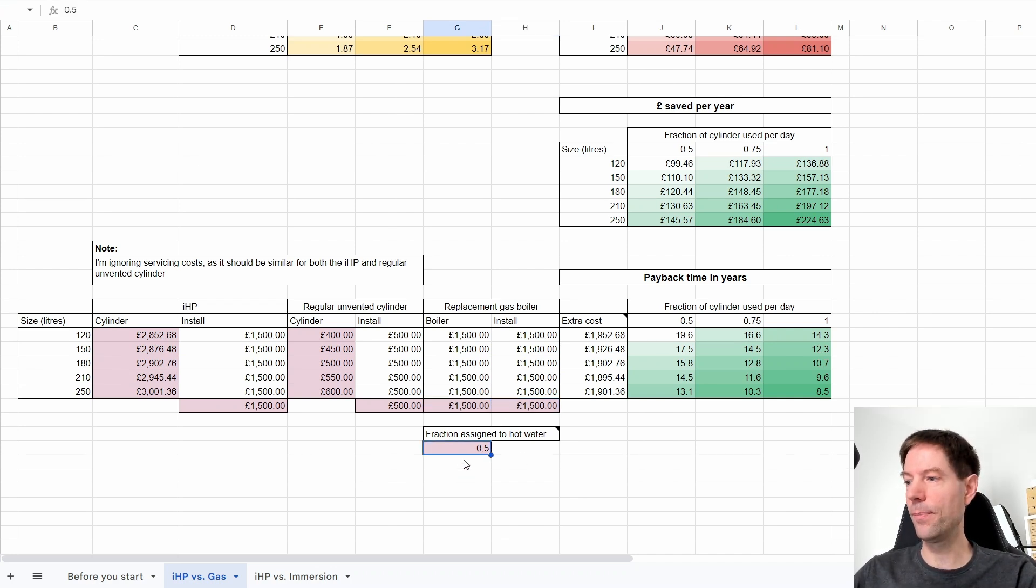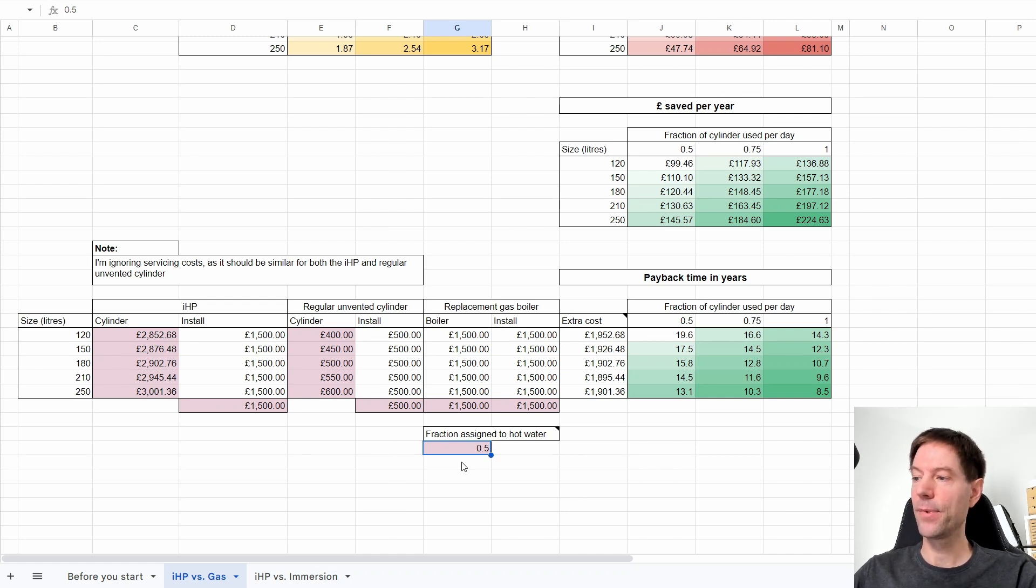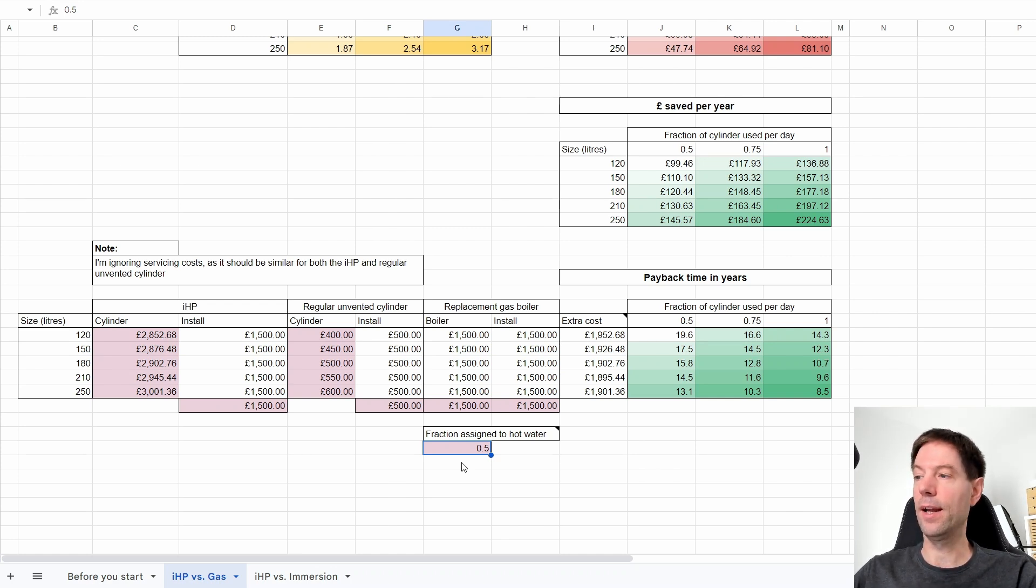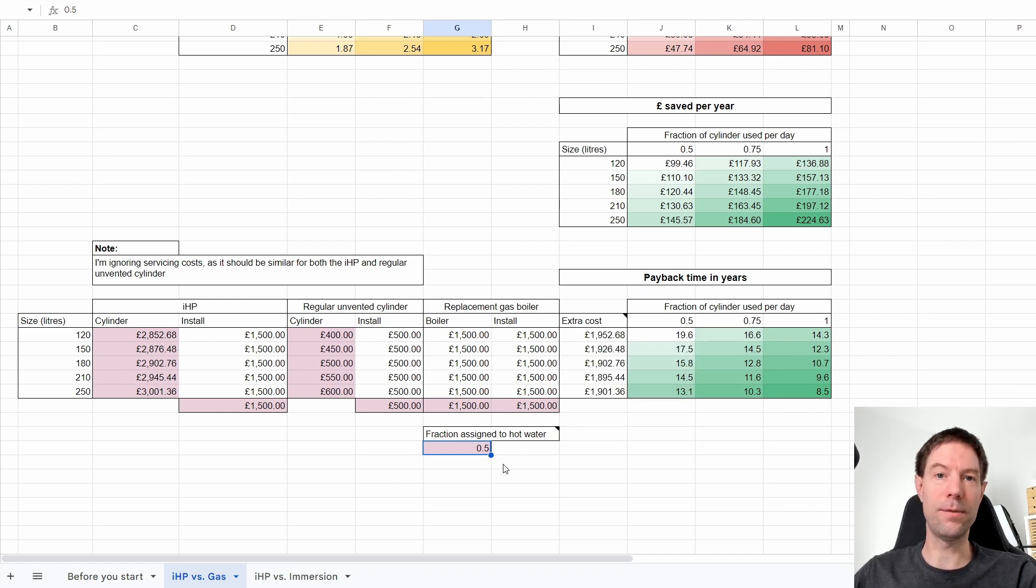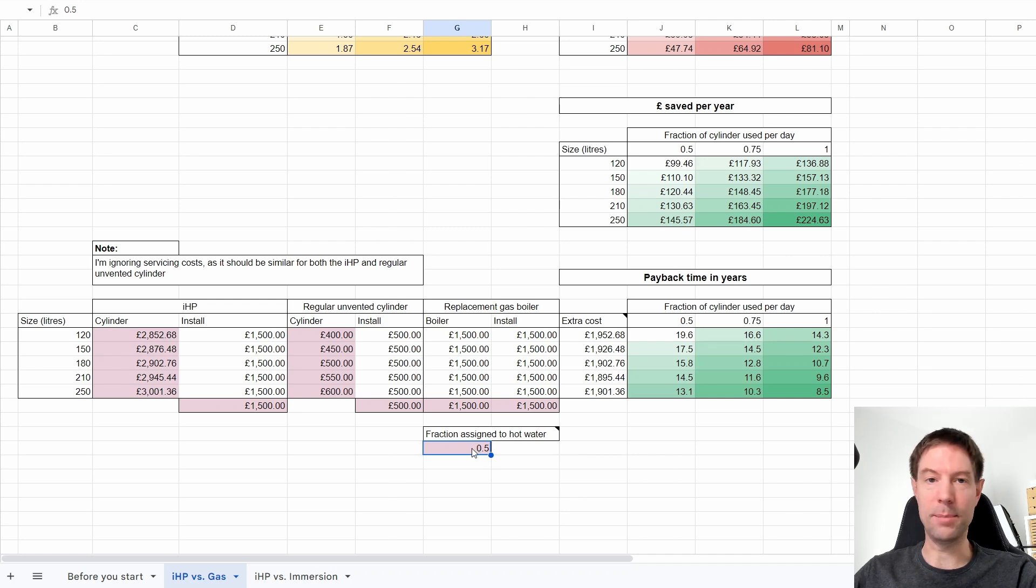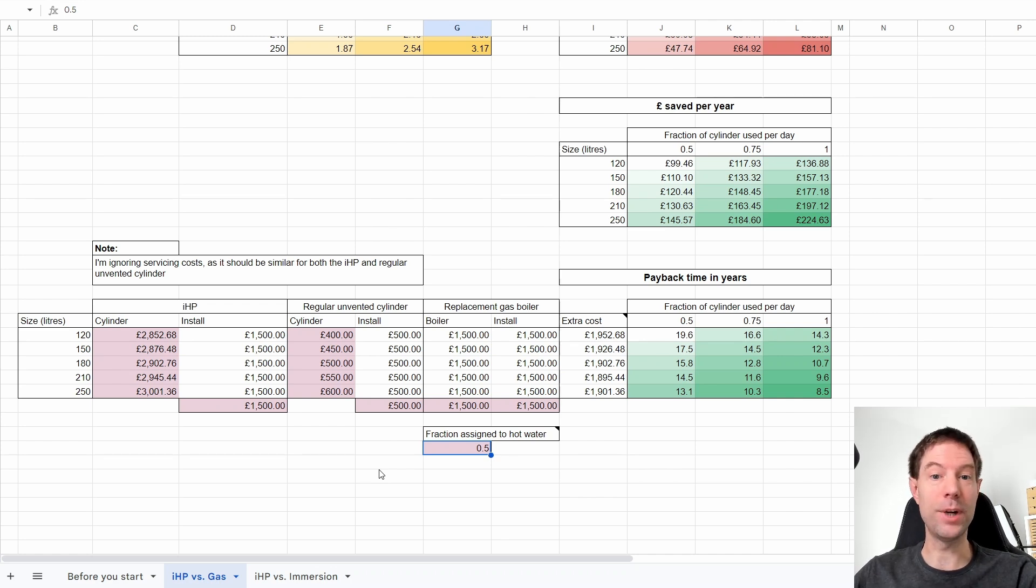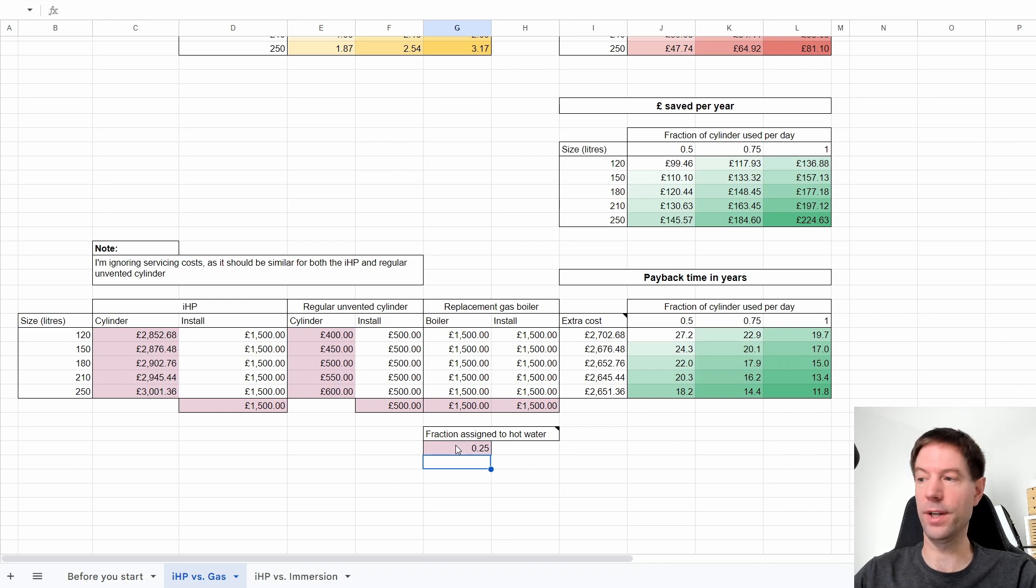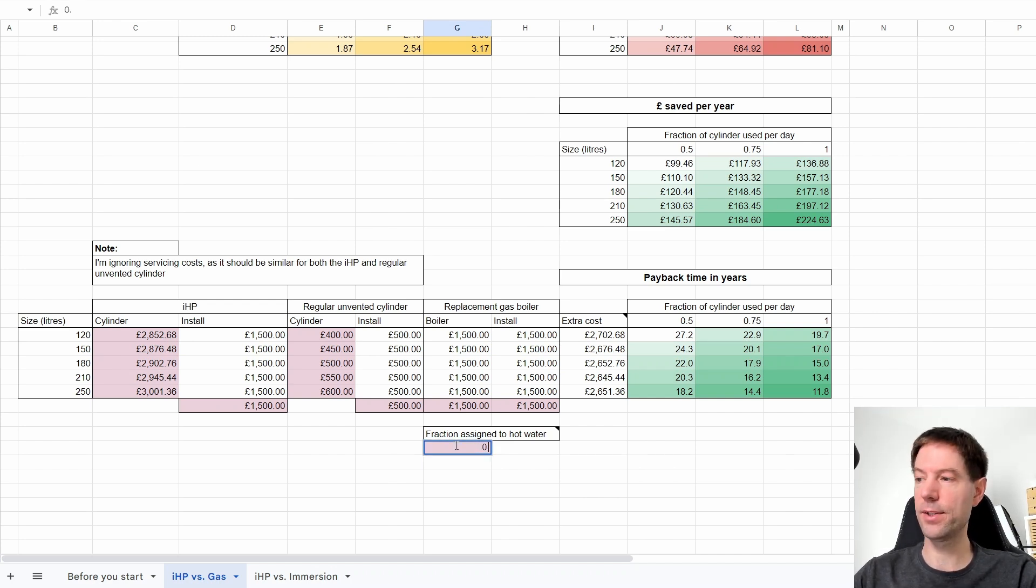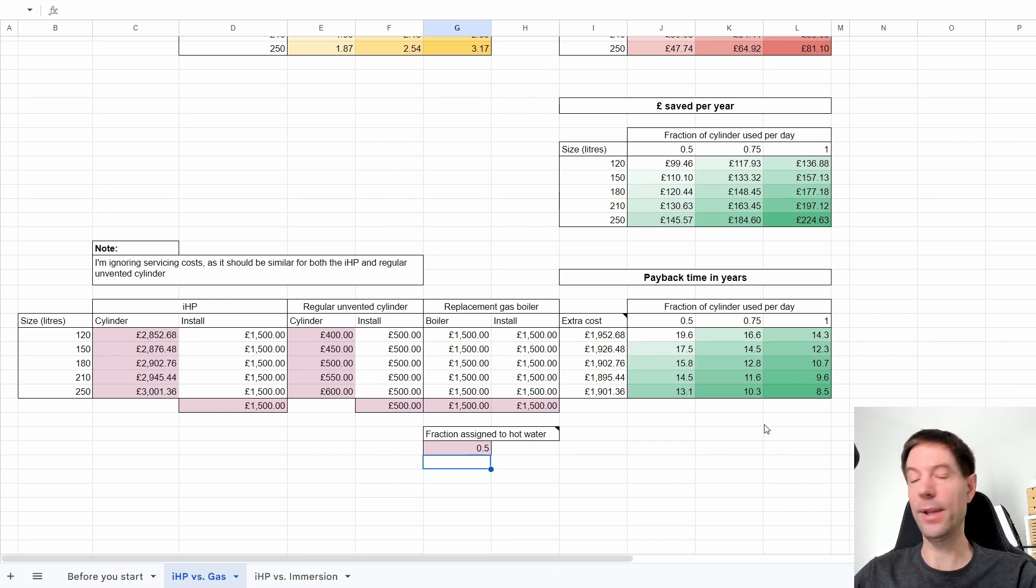What I've got here, and this is the important thing, is this fraction of the replacement gas boiler which you're assigning to the hot water. What I mean by that is if you were replacing your heating and hot water system, and the alternative was to do that with a gas boiler, you could consider half of the gas boiler cost to be offset against your air-to-air heat pump system and half against the IHP. So that's what I mean by 0.5 here. However, if your opinion was that your gas boiler was only used a quarter of the time for hot water and three quarters for heating, you could put 0.25 here.